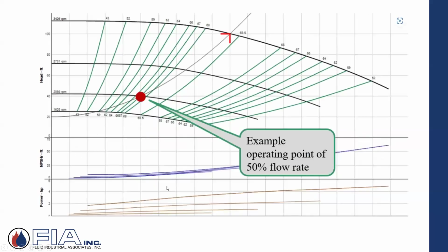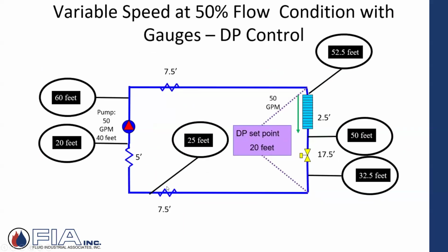So with the variable speed here, my pump is down to 50 gallons a minute, but now I'm only developing 40 feet of head at that reduced flow. With the constant speed, originally I had 115 feet of head. So I had that fixed constant speed. Now I have variable speed. I'll change the RPM.